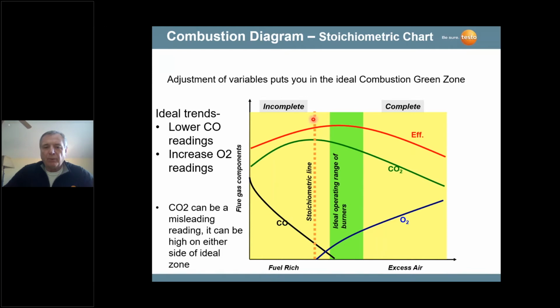It's also an area where we have a pretty high combustion efficiency rating, but we don't want to be here because of high concentrations of carbon monoxide. If we reduce the air in the burner and we happen to pass over into the complete fuel-rich mixture, then we really have some serious issues. We have high concentrations of CO, and I'm talking thousands of parts per million of CO. We have no oxygen. Our instrument, our combustion analyzer, may be measuring 0 or 0.3, 0.5% oxygen. And like I said, typically you're measuring 3 to 6% oxygen here, and maybe higher on the residential furnaces, 7 or 8 or 9% on the residential furnaces.